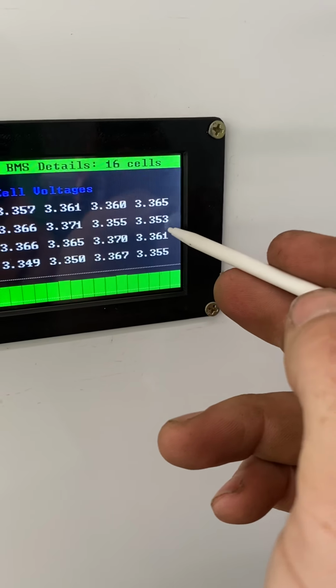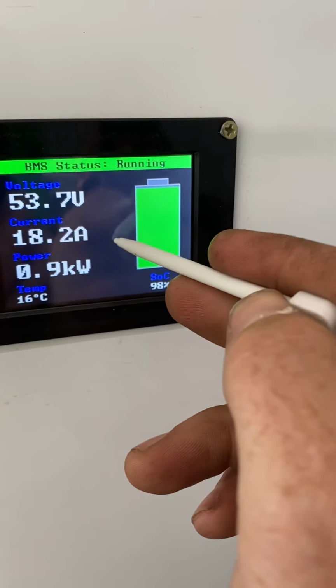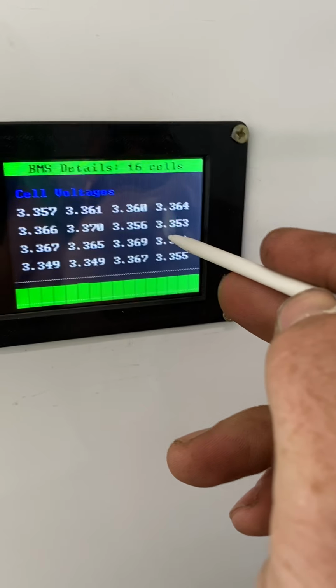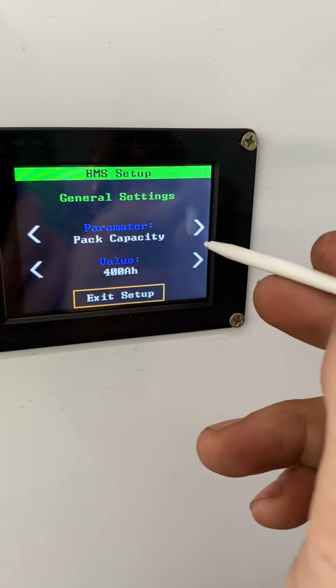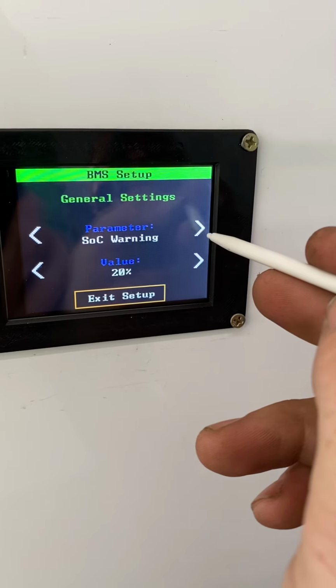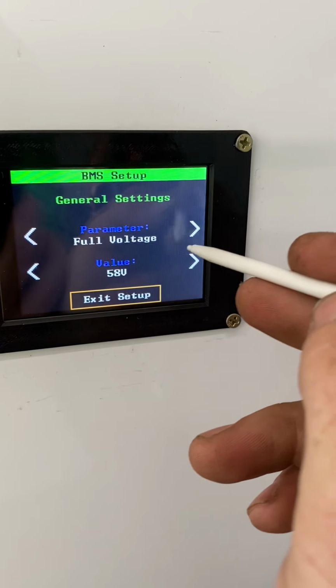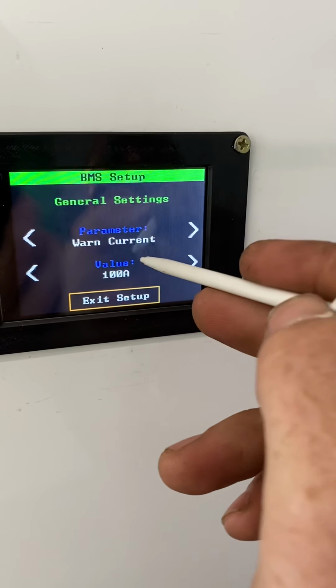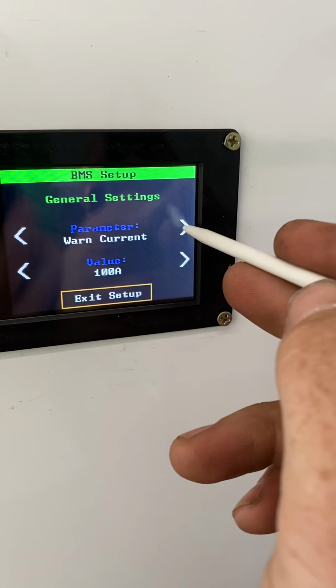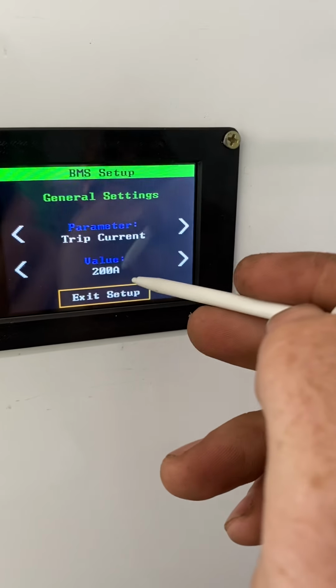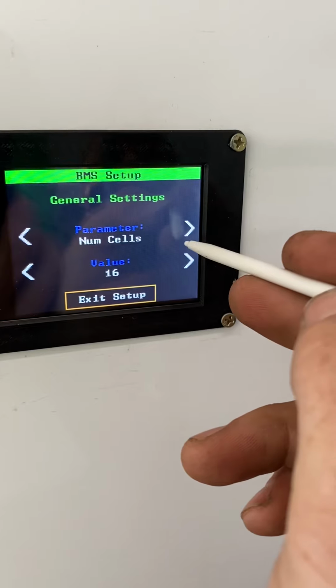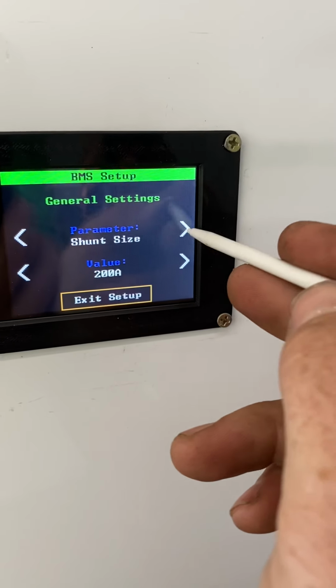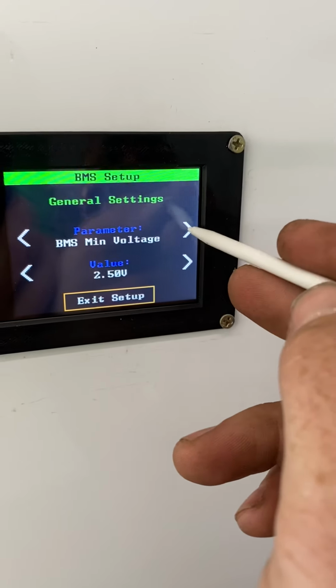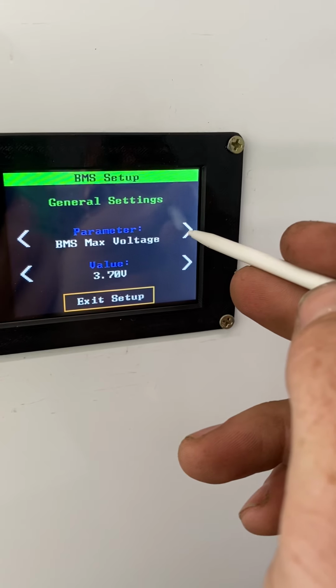So, yeah, if I hold it, all the settings come up: pack capacity, state of charge warning, full voltage 58 volts, warning current - so if it's drawing more than 100 amps, it'll warn me, and if it goes over 200 amps, it'll trip. 16 cells, shunt size 200 amps, minimum voltage 2.5 volts, max voltage 3.7.